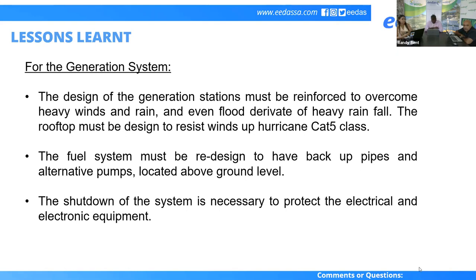Because we already experienced a Cat 5 class hurricane, and this is a high level event, the fuel system is going to be redesigned. We're going to have backup pipes and alternative pumps, and locate them above ground level. This is because with heavy rain we have flooding in the area, and usually these systems are below ground, so we have to change the design completely.